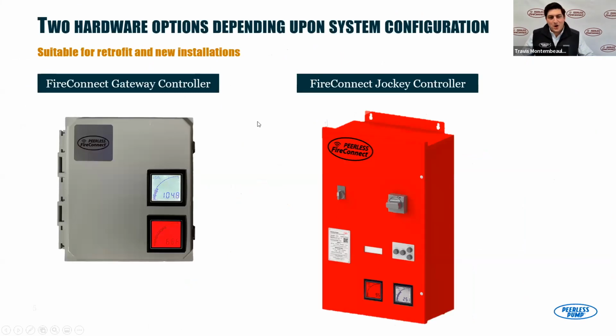So from a hardware standpoint, we showed you on that previous slide in the center, the FireConnect gateway controller, and that's your IoT brains of your system. That's how we get that data. That's all that data that's trapped in the 4 walls of the pump room. That's how we get it out. Cellular connection up to the cloud, so on and so forth. This gateway controller typically connects via Modbus to the main fire pump controller, and via Modbus to a jockey pump controller. Now, the jockey pump controllers, as I just mentioned, a lot of times don't have that Modbus option, or it's a retrofit requirement.